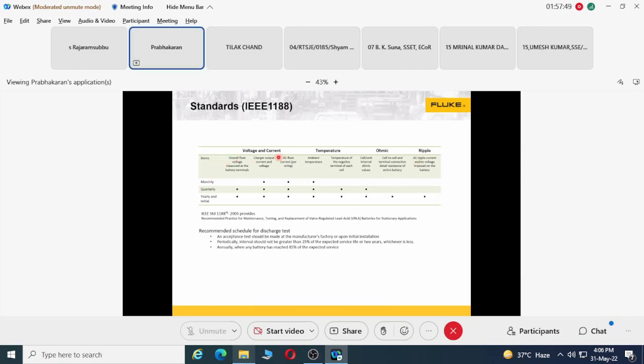For voltage and current, the overall float voltage and charger output current and voltage are required to be tested. The overall float voltage of your battery system needs to be tested, and DC float current also needs to be tested, because this is the string current, or overall current taken from the system.